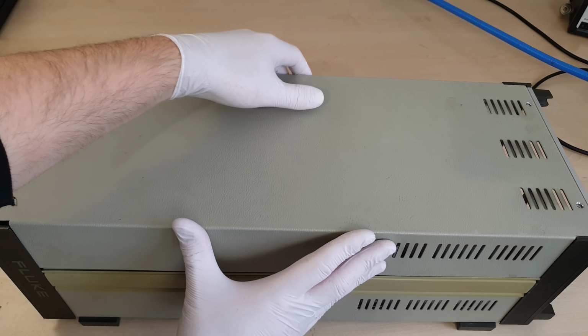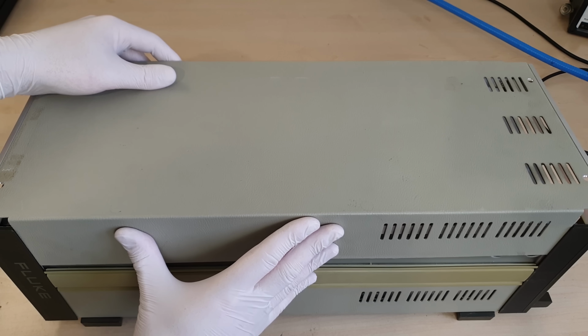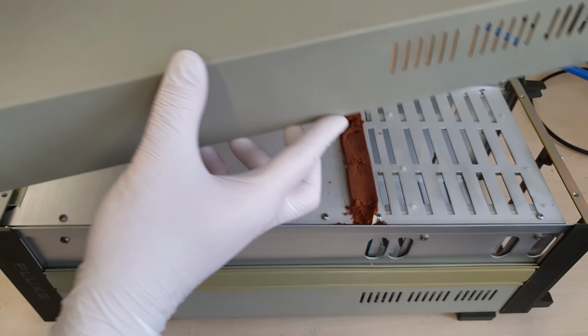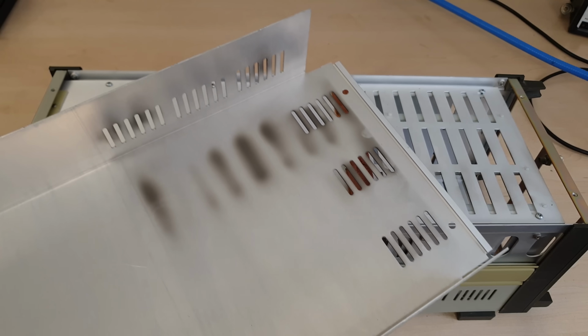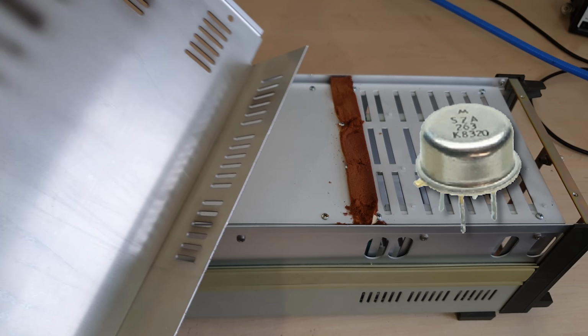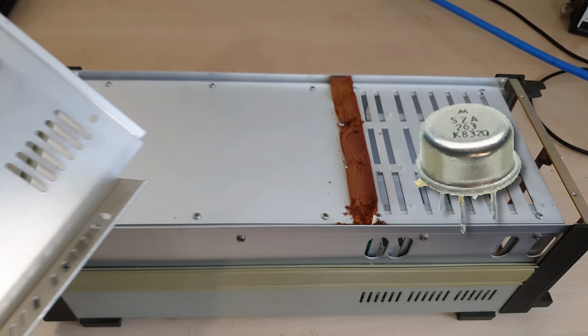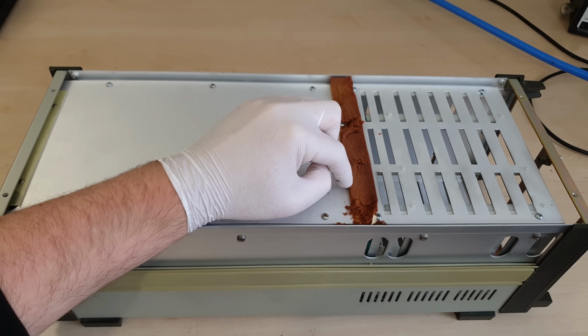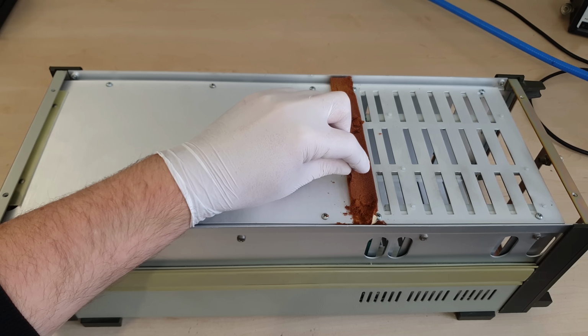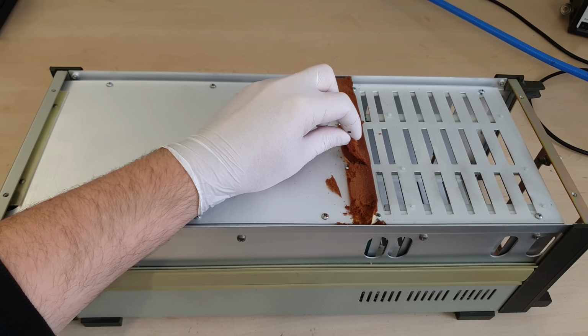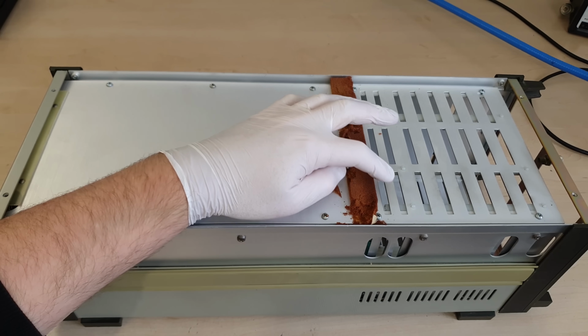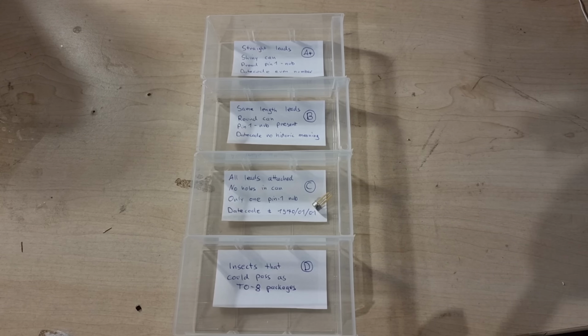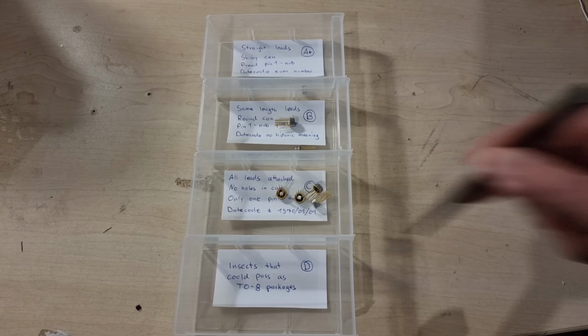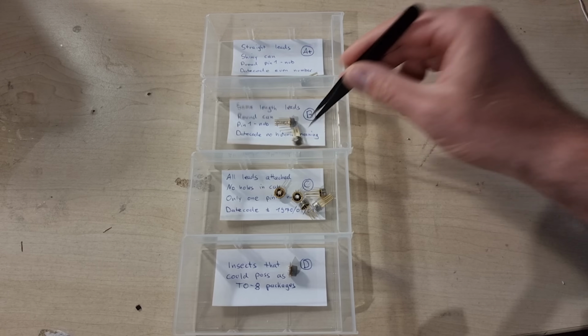Alright, time for us to leave the boring management area behind and to unbury the business end, the reference assembly. Fundamentally, this product is actually based on the same SZA263 Zener diode that's largely responsible for my calibrator's good performance. So how is it that this DC voltage standard used to be the official recommended calibration source for that calibrator? What makes it better? Well, it's more than likely that they are doing binning at the factory. With the creme de la creme going into DC voltage standards, the second best going into calibrators, the third into multimeters, and the rejects somehow surface on eBay eventually.